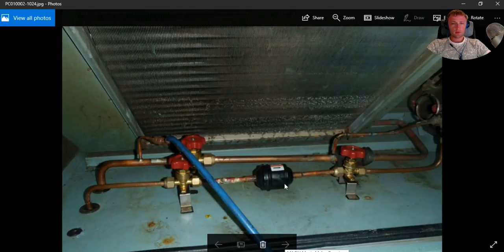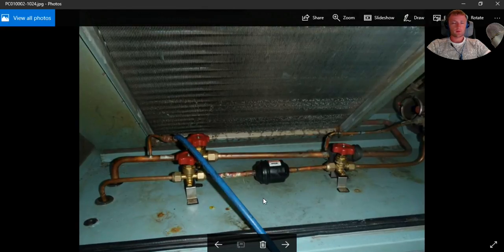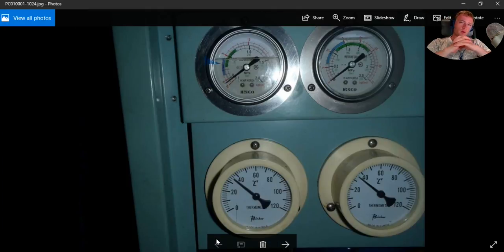And this one, it's the filter drier, it's a filter which removes any moisture from the system. Isolating valves if you like to isolate. And here also is one isolate valve if you like to change your heat exchanger. It's better to have more isolate valves, and for that reason they must be properly set in position, must be calculated. So if you like to change something, you do not need to drain your freon.